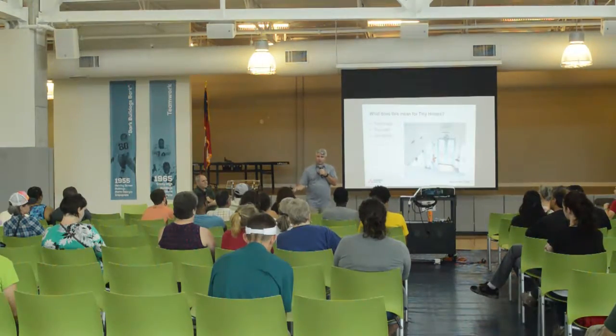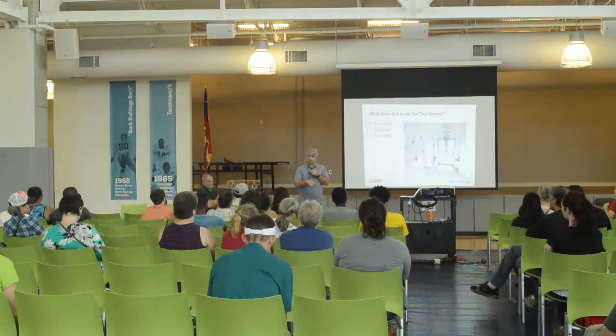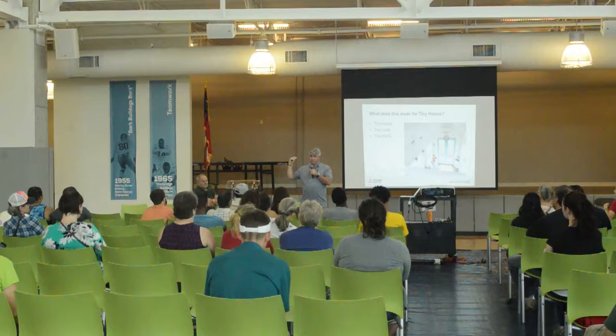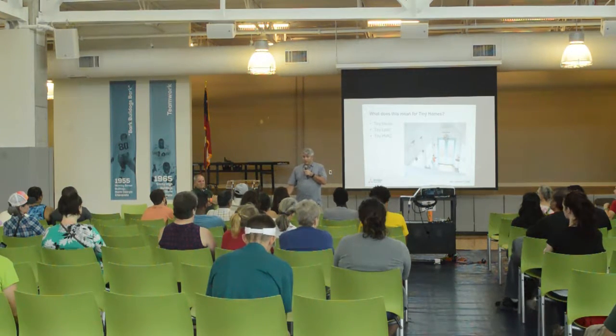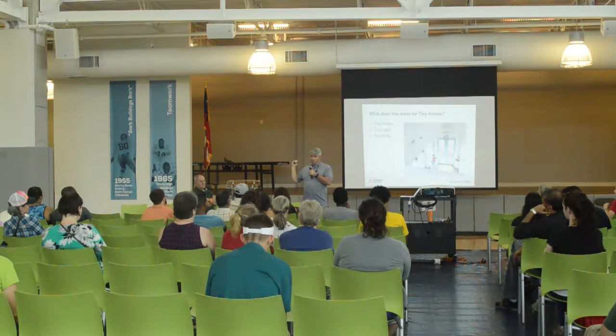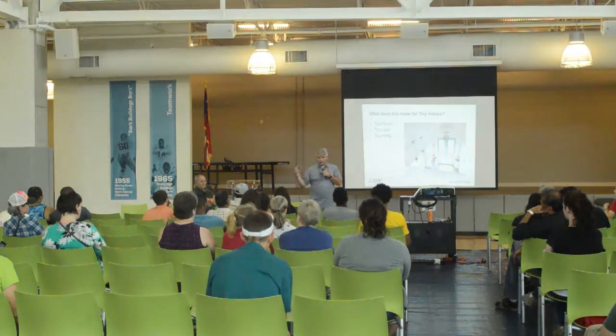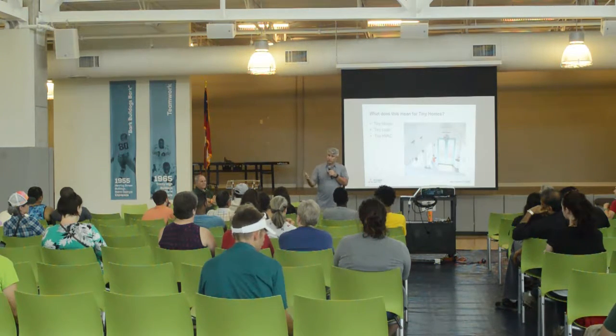We can actually connect up to 8 indoor units to one outdoor condenser using what we call a branch box - sort of like a manifold in plumbing. At that point, we run refrigerant from the outdoor unit to the branch box, and it controls how much refrigerant goes to each indoor unit. So again, one outdoor unit and up to 8 indoor air handlers.